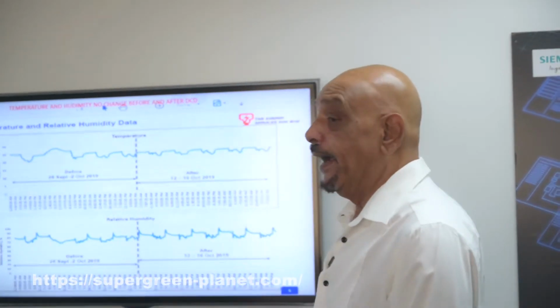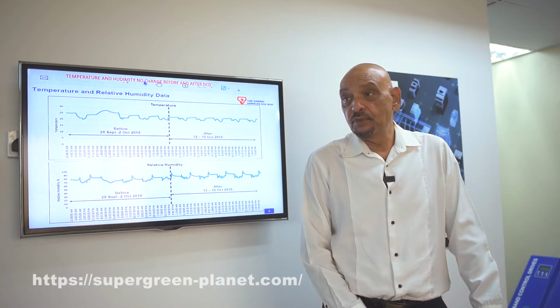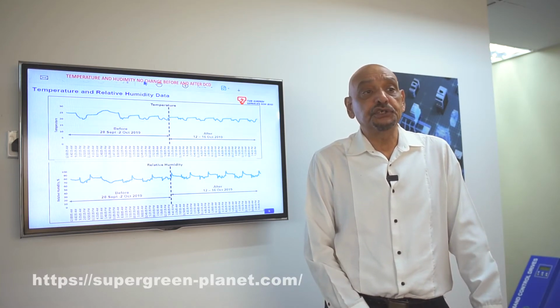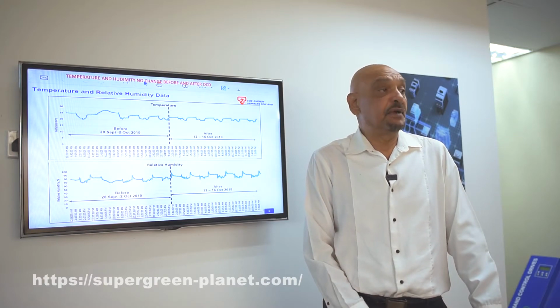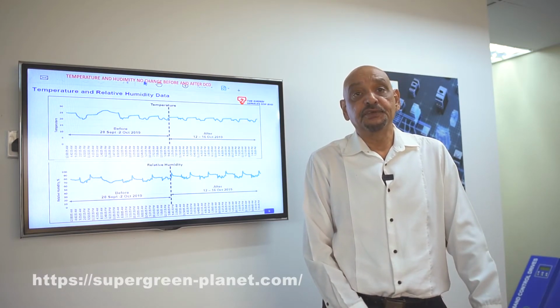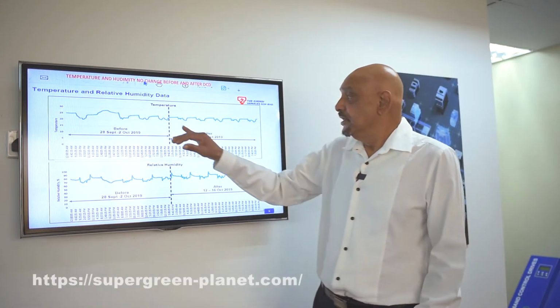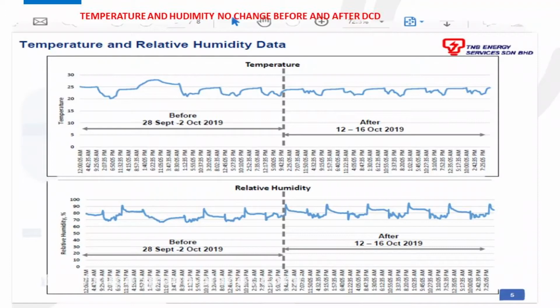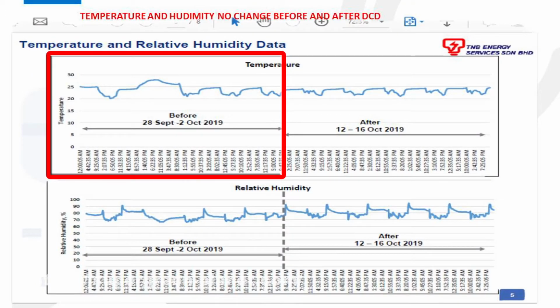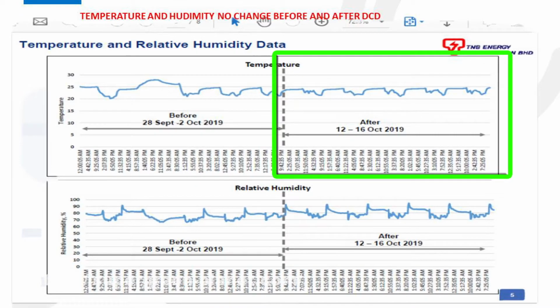The first week, all your baseline measurements were done, and after that 1 week period, we installed demand control drives, which are temporarily installed. We wire the sensors as well as the system in, and electrical as well as temperature parameters continued to be measured. Now, what you see here is the temperature profile before DCD was installed, and over here is the temperature profile after the installation of DCD.